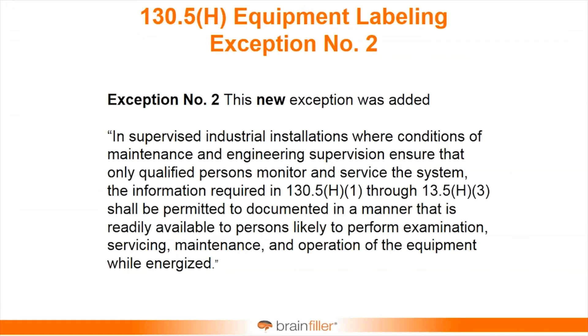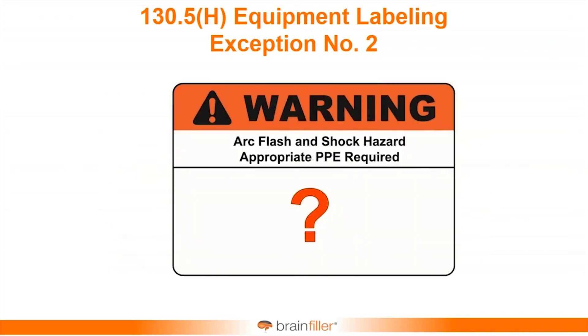The new exception simply states: in supervised industrial installations, with conditions of maintenance and engineering supervision, and where qualified persons are the only ones working on the system, the information in H1 through H3 — that's the voltage, the arc flash boundary, and the PPE — can be documented and made readily available to people performing energized work. The concept is you don't have to put anything on your label.